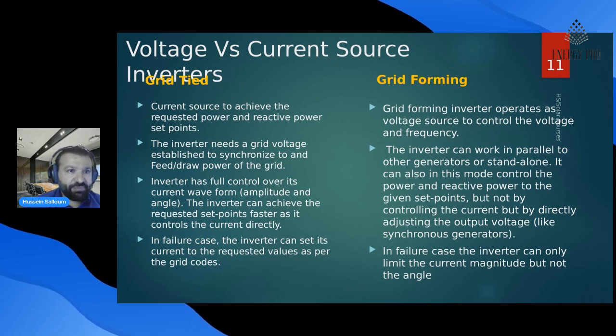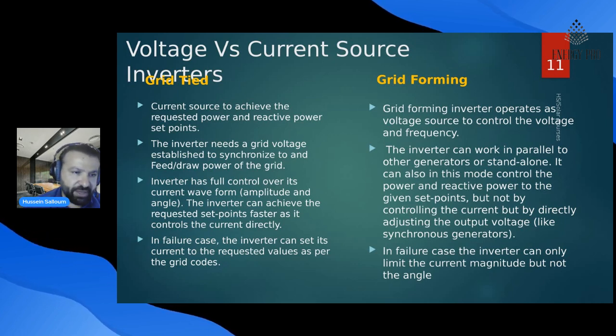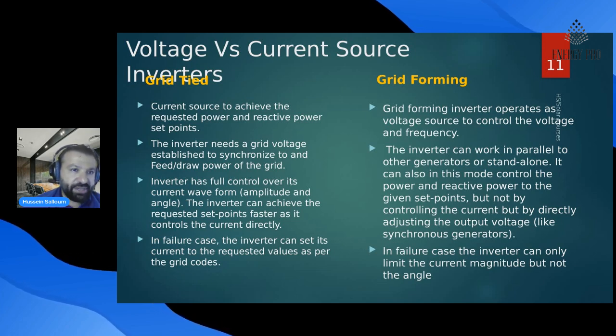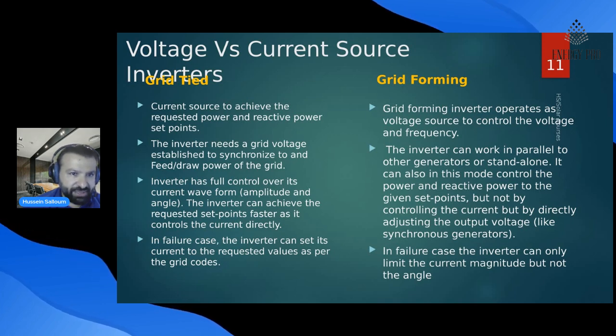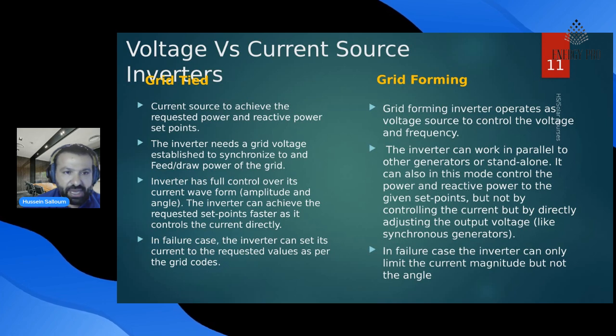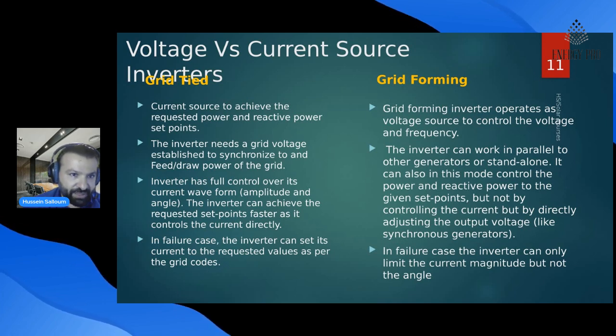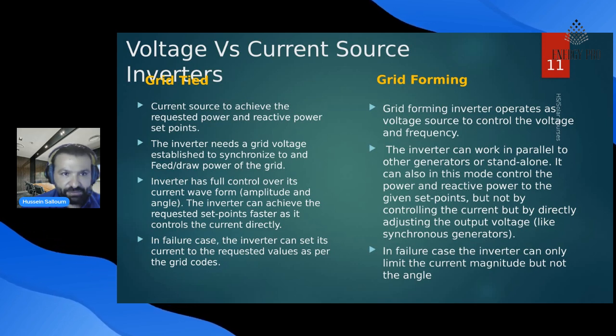This leads us to the next slide where we have the inverters that are put in front of the PV modules. One type is a grid tied inverter and the other type is a grid forming inverter. So a grid tied inverter basically is a current source inverter that achieves the requested power and the reactive power set points. So the grid tied inverter needs a voltage from the grid. And this voltage will be used to synchronize and to draw the power to the grid. The inverter has the full control over its current. And here it can achieve the requested set points faster as it controls the current directly. In case of failure, the inverter can set its current to the requested values as per the grid requirement. This is the grid tied type.